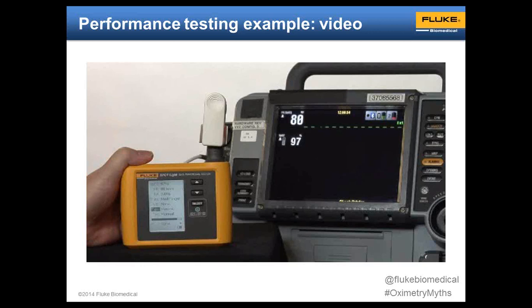And so we have 97% on the functional tester and 97% on the monitor. What we would do at that point is lower it to whatever our alarm threshold was. Let's say it's 94, and then we would check to make sure that the monitor alarmed appropriately.